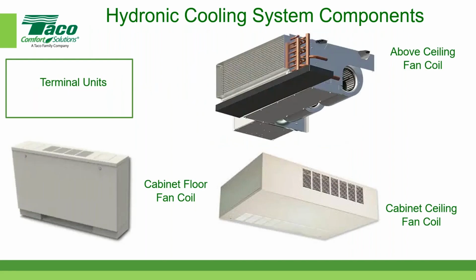So for terminal units, we can have fan coils, and you can get the type that fit above the ceiling, and they don't have any cabinets over them. They're probably the least expensive, but they do have a cooling coil up here. If it's a four pipe unit, it might have a separate heating coil. This one perhaps just has a cooling coil, has a drain pan, because as the moisture drips off this coil it is collected in the drain pan, and then you have a condensate pipe that goes to a condensate drain somewhere. You can also get them with cabinets on them, fan coils with cabinets.